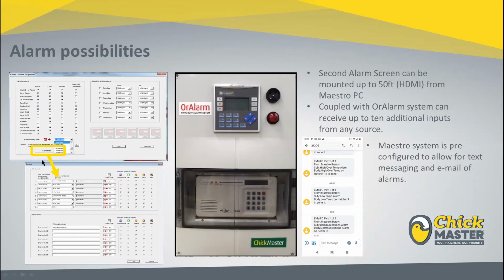And then when you're configuring users, you can create what's called tiered notifications. So maybe I let my maintenance man get the first notification by selecting time 0, which means there will be no delay. He gets notified right away. Maybe I let the backup maintenance guy get the second one by giving him a times 1, and then if I want to be notified later, I might be a times 2 or times 3, giving them a chance, hopefully, to indicate that they are working on the alarm by acknowledging it with the acknowledgement button. Again, if they do acknowledge that, then the remainder of the notifications that go out will let you know they've been acknowledged by somebody. So somebody is working on it. And down here you can set up the contacts with the delays like we discussed. And as you can see, we let you put in either email or text message phone numbers.